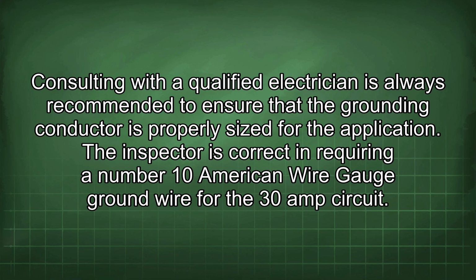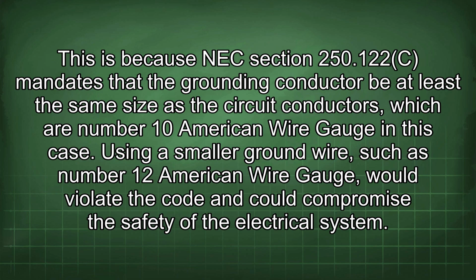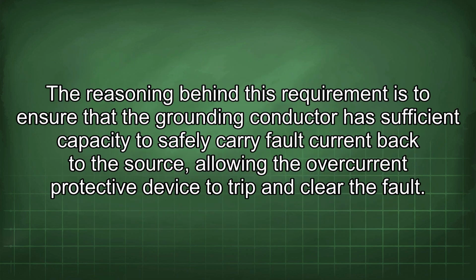The inspector is correct in requiring a number 10 American wire gauge ground wire for the 30 amp circuit. This is because NEC section 250.122(C) mandates that the grounding conductor be at least the same size as the circuit conductors, which are number 10 American wire gauge in this case. Using a smaller ground wire, such as number 12 American wire gauge, would violate the code and could compromise the safety of the electrical system. The reasoning behind this requirement is to ensure that the grounding conductor has sufficient capacity to safely carry fault current back to the source, allowing the overcurrent protective device to trip and clear the fault.